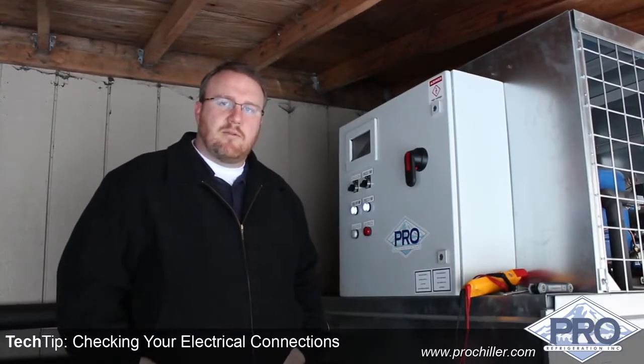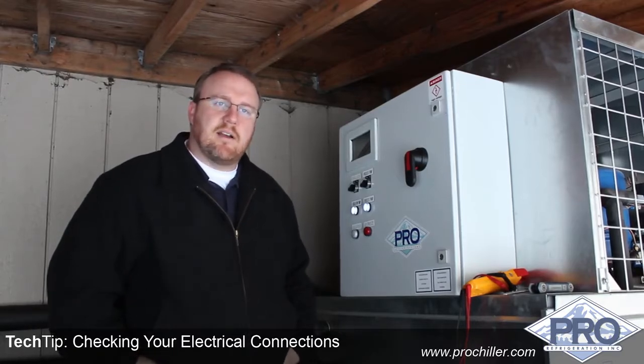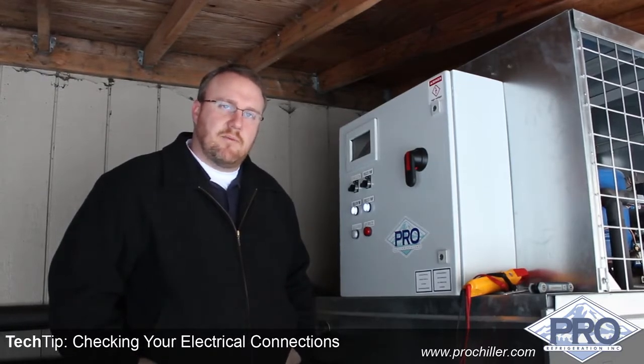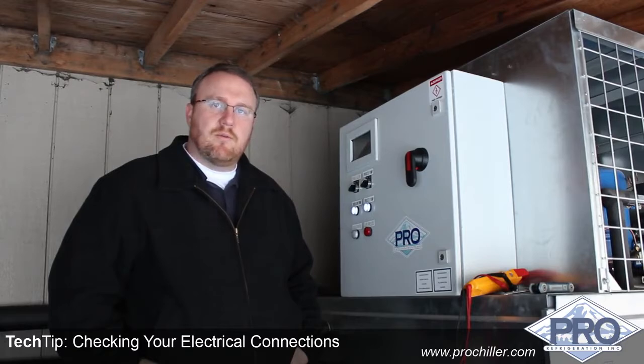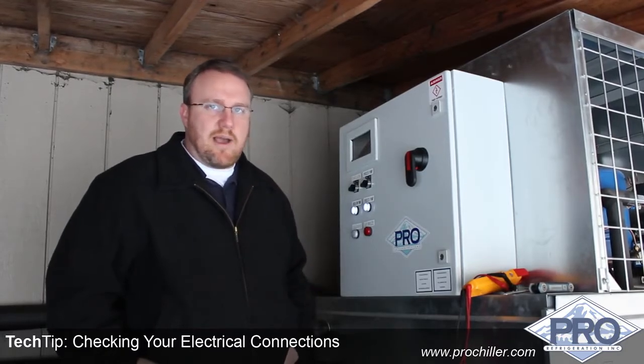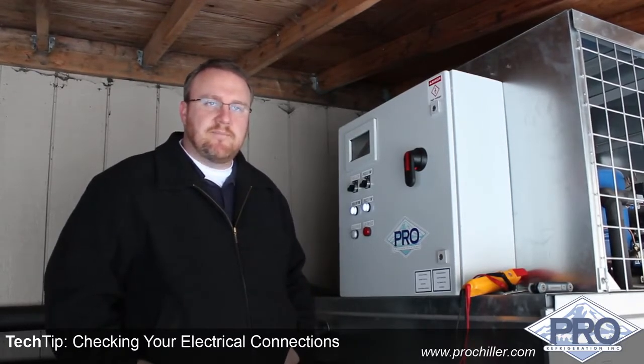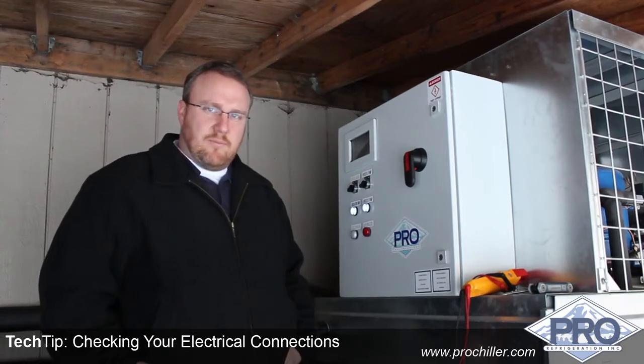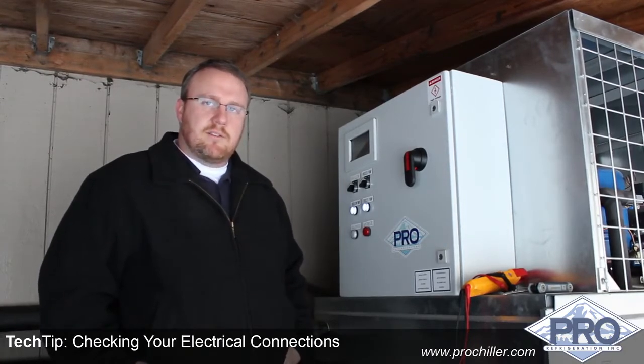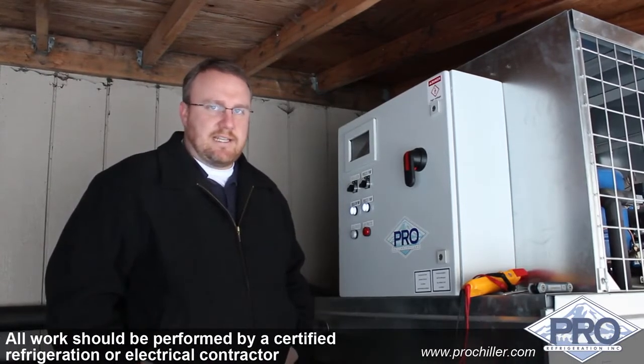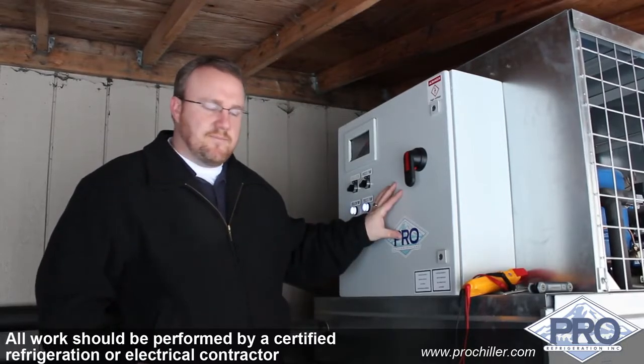This is the Pro Refrigeration Tech Tip. For this technical tip, we're at 7 Seas Brewery working with their 5 horsepower MA series chiller system. In this tech tip, we're going to cover checking your electrical connections for tightness inside of the electrical control panel.